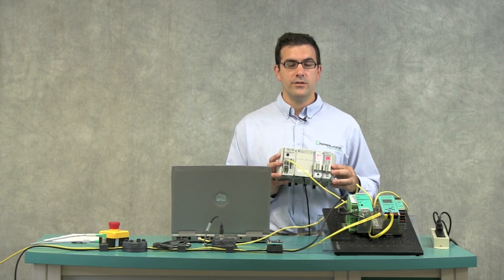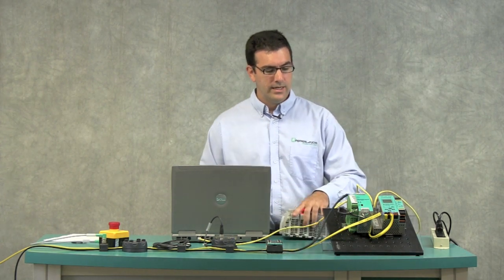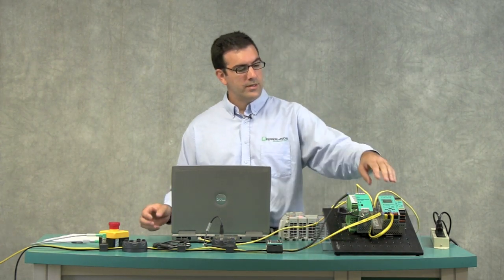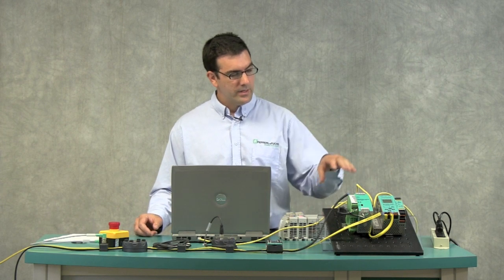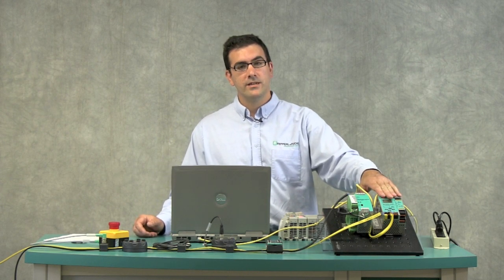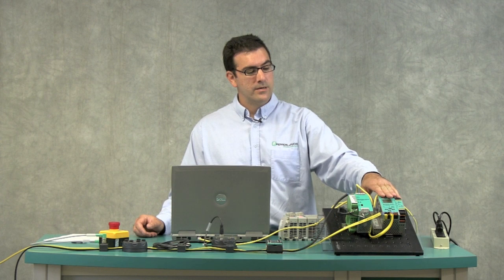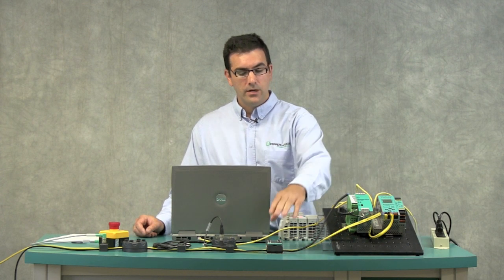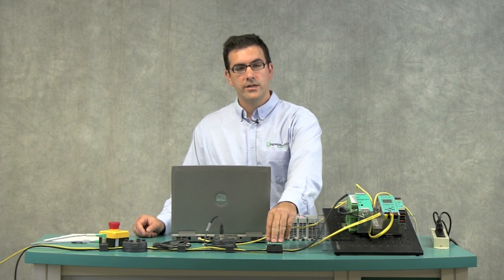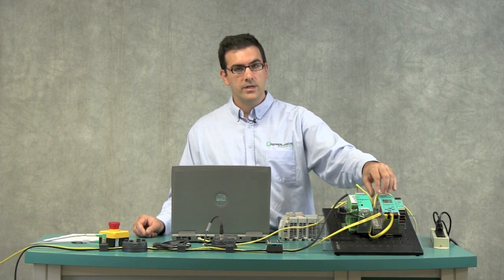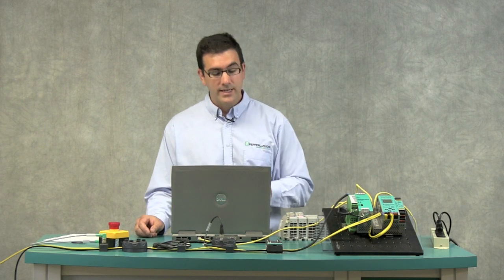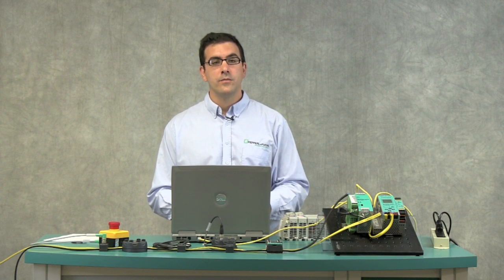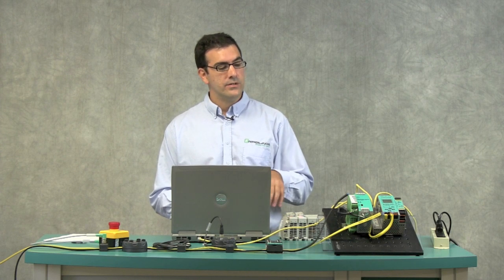I'm going to be using the L32E PLC and programming the AS Interface gateway. The gateway has been completely configured with the IP address, subnet mask, and gateway. The network has been configured and set up, and I used a store and run on the gateway to make sure everything was set. So the next thing to do is go into my RSLogix 5000 software and start the programming. I'm going to be using version 20 of the RSLogix 5000, which allows me to use the EDS file to completely configure the gateway.